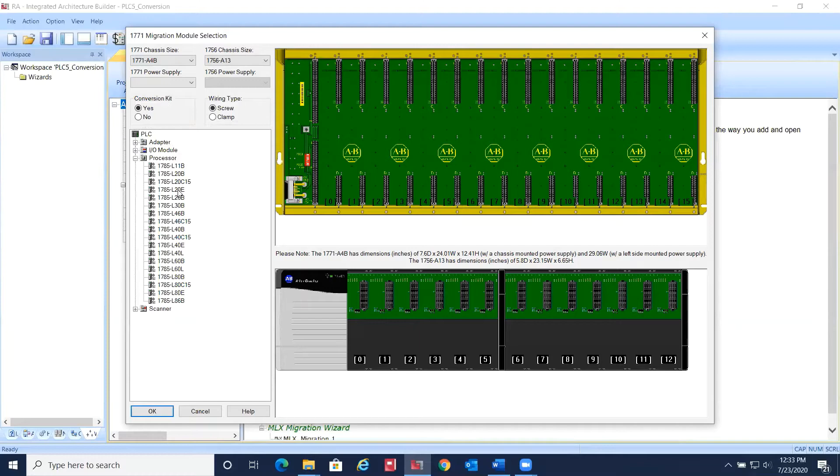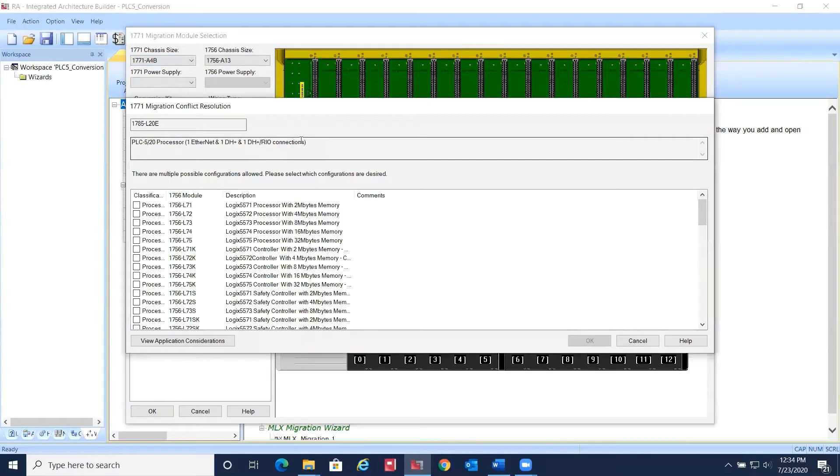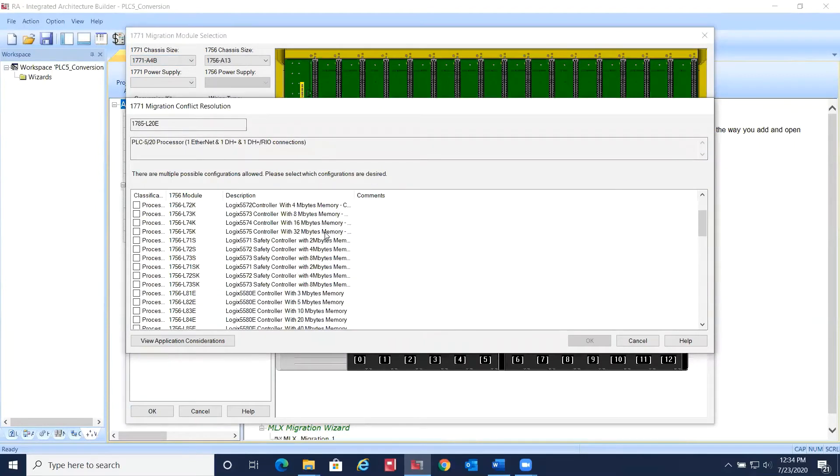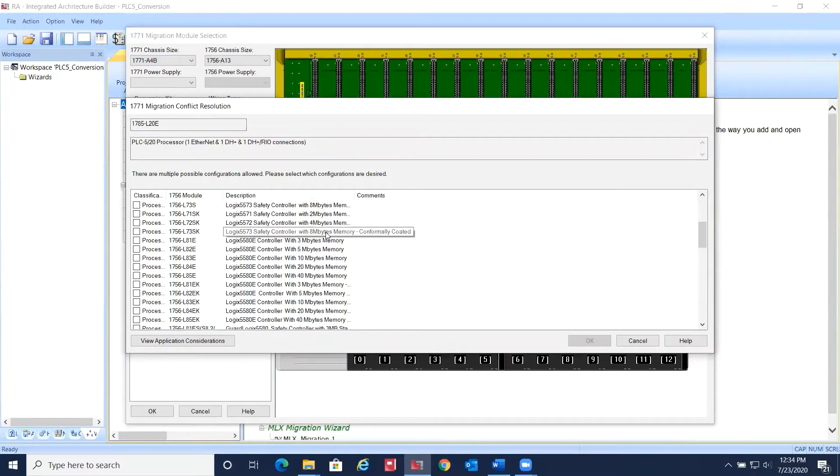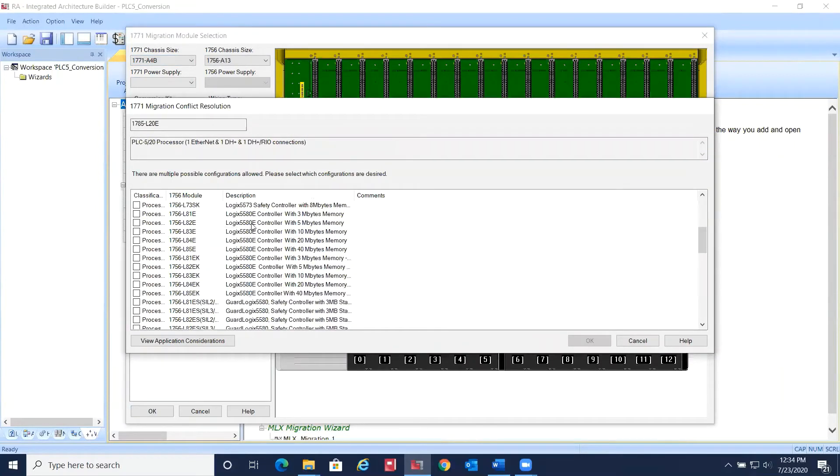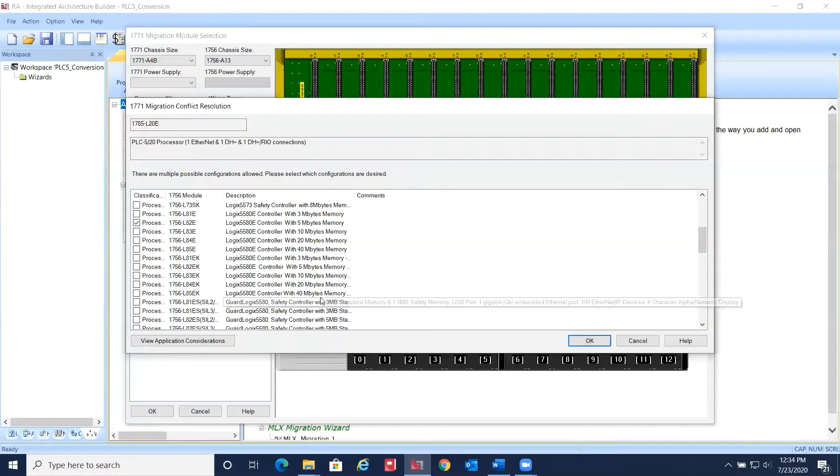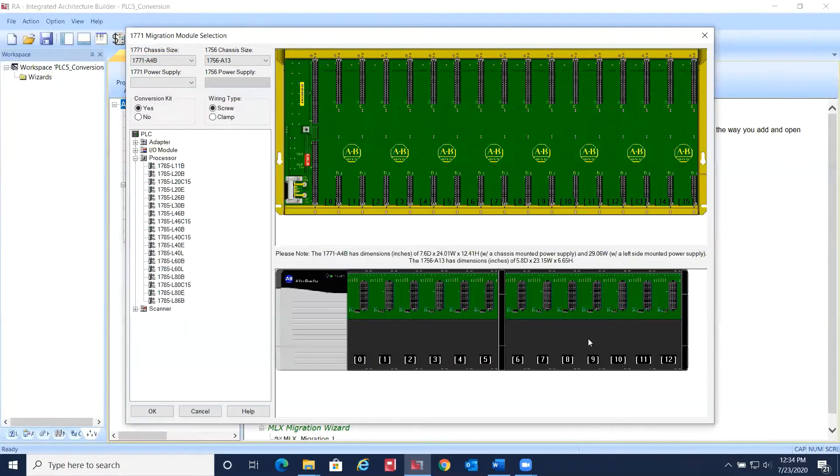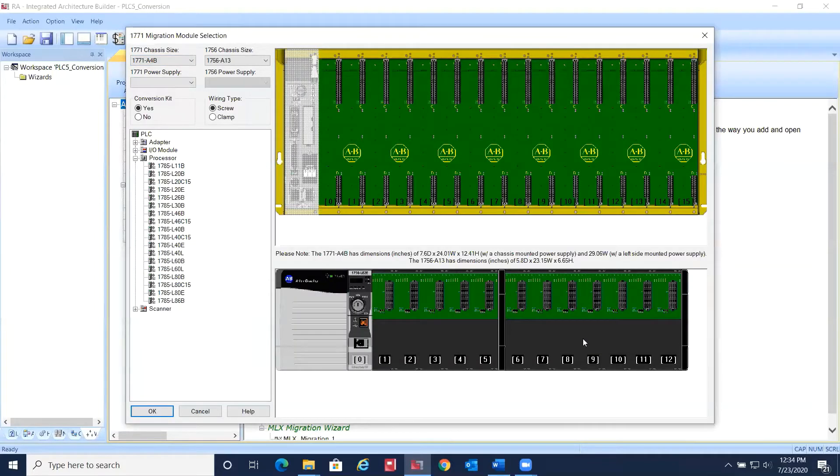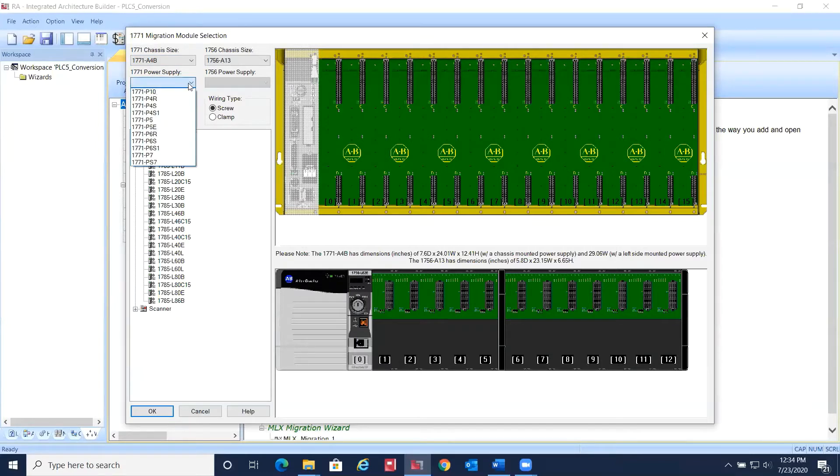Select the existing PLC5 processor from the list of available processors and drag and drop it into the PLC5 chassis. Now select the ControlLogix processor that you wish to replace it with. You can choose from L7 or L8 processors. The L8 processors come with an integral Ethernet port. Here we'll choose 1756-L82E.